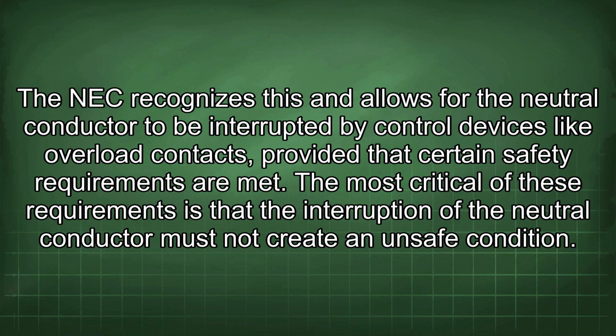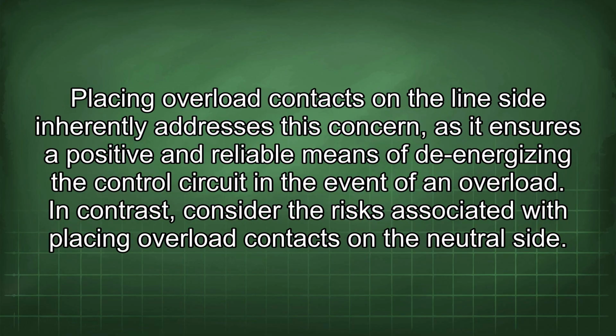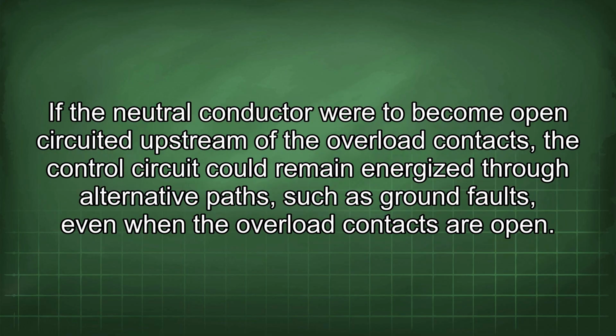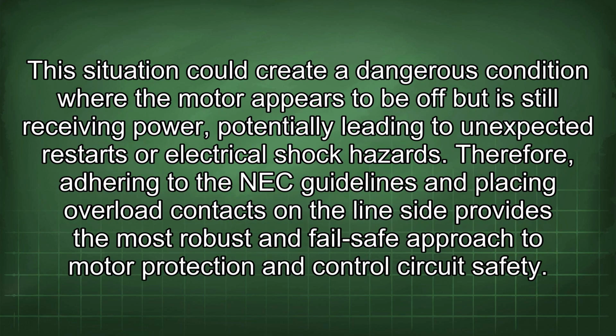The most critical of these requirements is that the interruption of the neutral conductor must not create an unsafe condition. Placing overload contacts on the line side inherently addresses this concern, as it ensures a positive and reliable means of de-energizing the control circuit in the event of an overload. In contrast, consider the risks associated with placing overload contacts on the neutral side. If the neutral conductor were to become open-circuited upstream of the overload contacts, the control circuit could remain energized through alternative paths such as ground faults, even when the overload contacts are open. This situation could create a dangerous condition where the motor appears to be off but is still receiving power, potentially leading to unexpected restarts or electrical shock hazards.